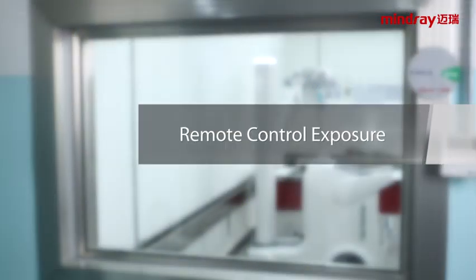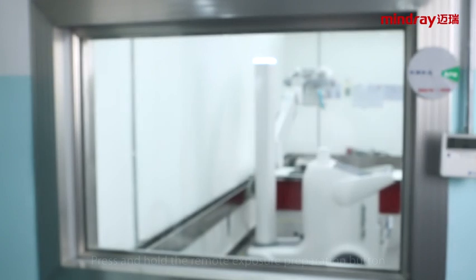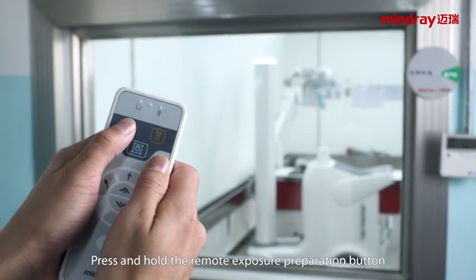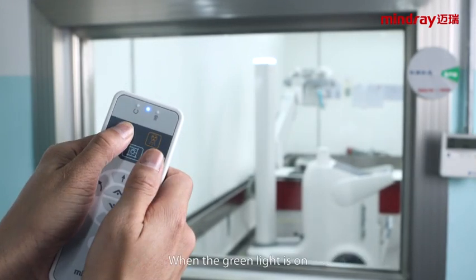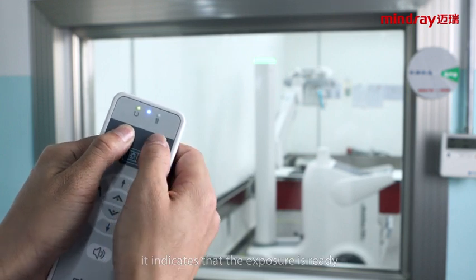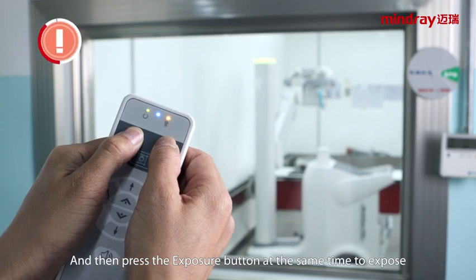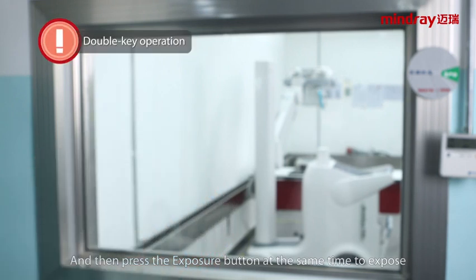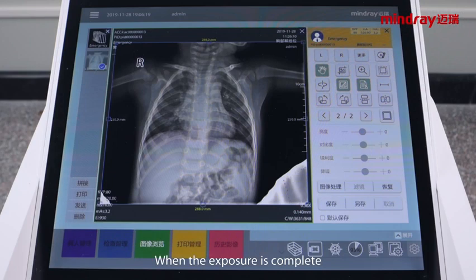Remote controller exposure. Press and hold the remote exposure preparation button. When the green light is on, it indicates that the exposure is ready, and then press the exposure button at the same time to expose. It needs the 2 keys to press together to make exposure. When the exposure is complete, the image browse screen is automatically displayed. Post-processing of images can be performed.